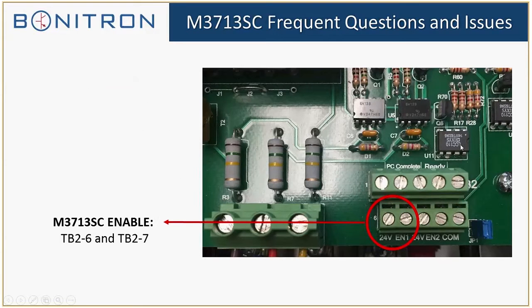Here's this picture just zoomed in. So you just either need to have a jumper here and be able to enable it on these 2 terminals. Otherwise, you'll get nothing on DC bus. The terminals up here are basically the output terminals, telling you once pre-charge is complete, once the unit's ready to operate. By and large, most customers, all they need is a ready signal, and they're good to go. So the M3713 is pretty solid, and other than enable, I haven't really gotten any issues on this unit ever.